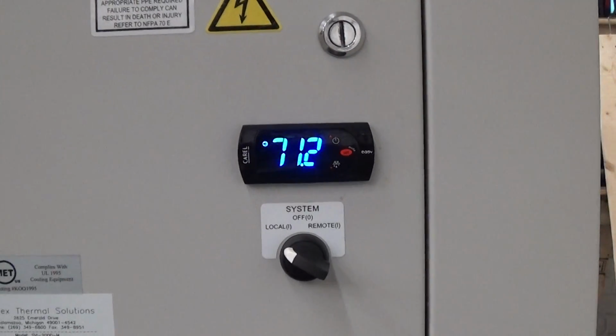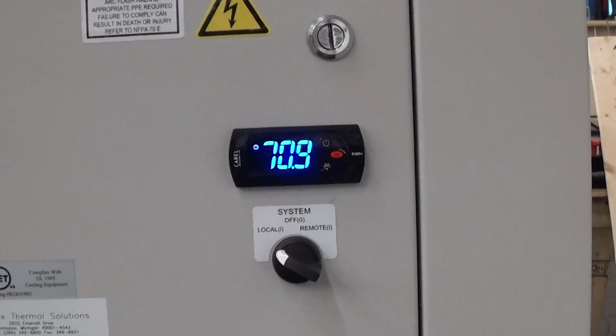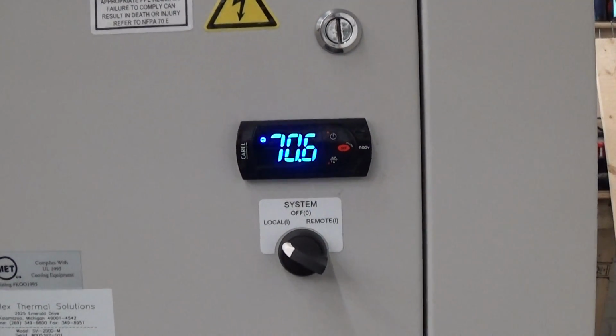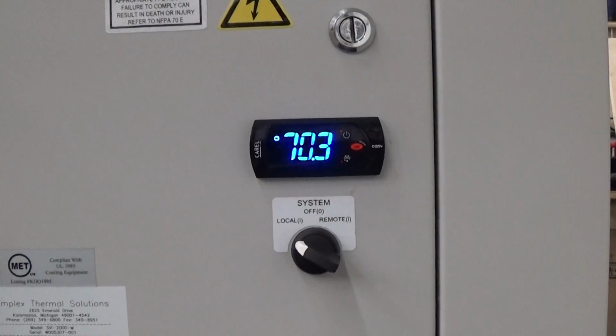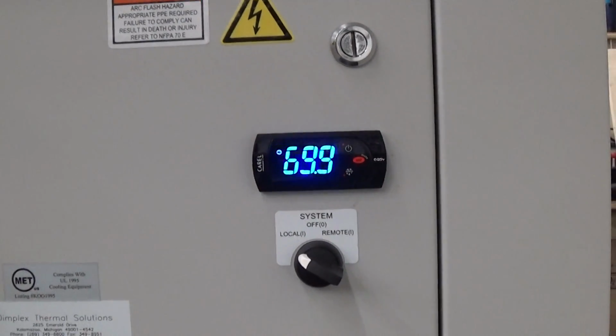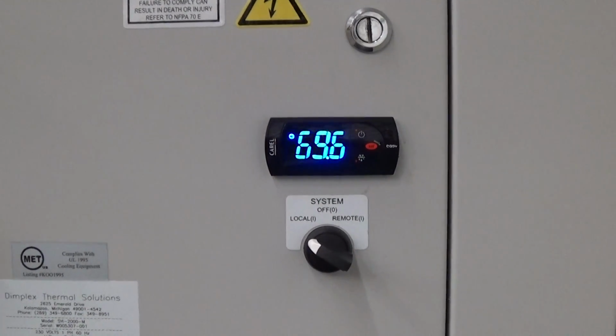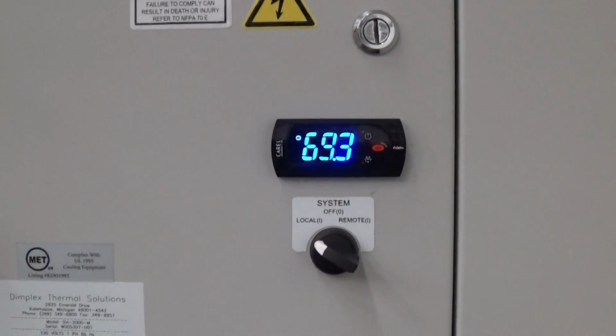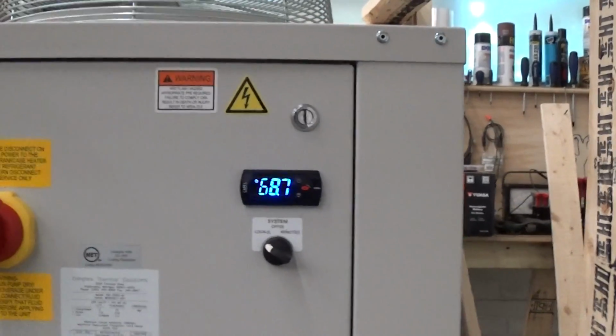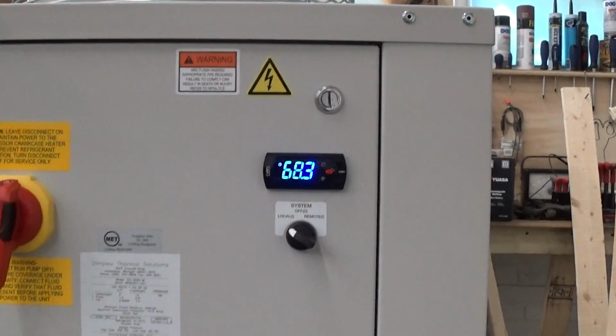So what does that mean? That means it's going to reach the set point and stop, in this case 30 degrees. And it's going to turn back on when we get 3 degrees above set point. If you can live with a wider differential than that, that helps keep the cycling of the compressor down.